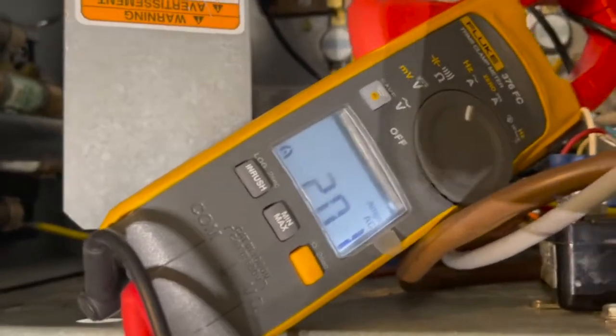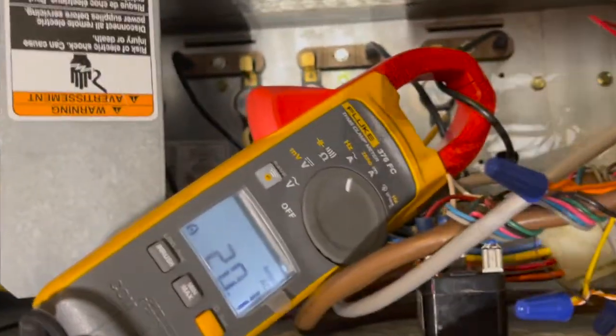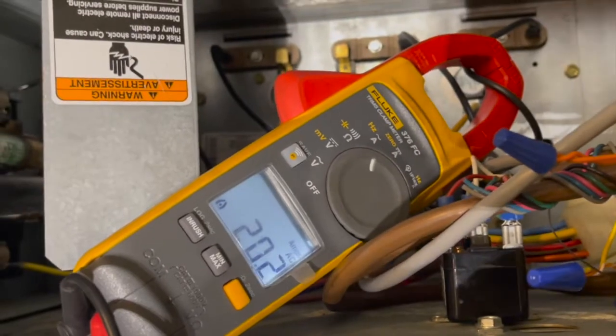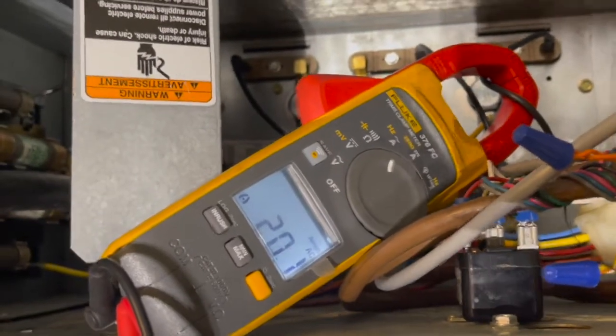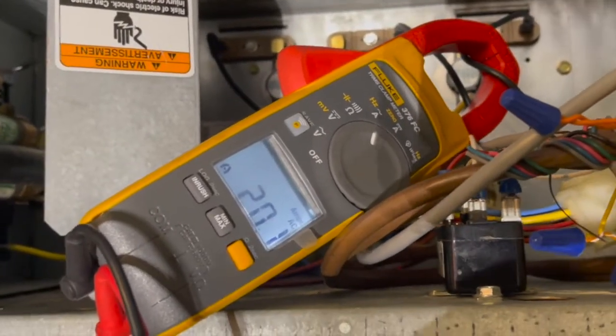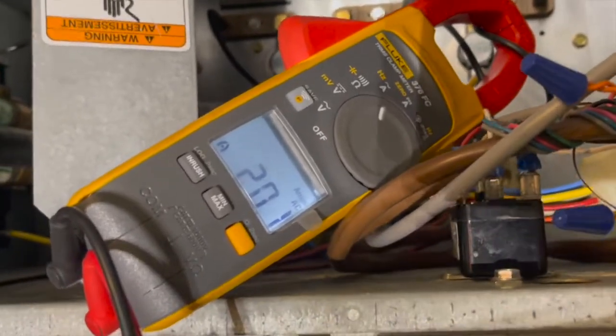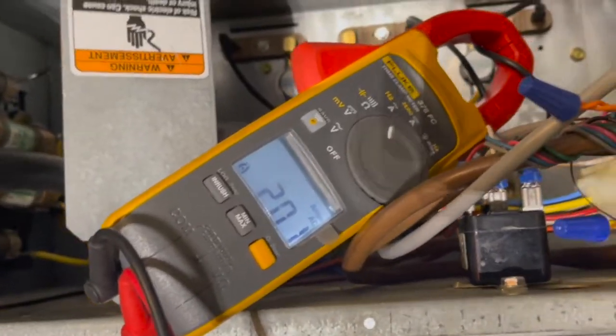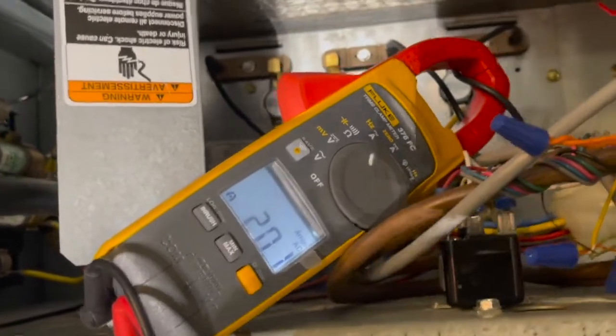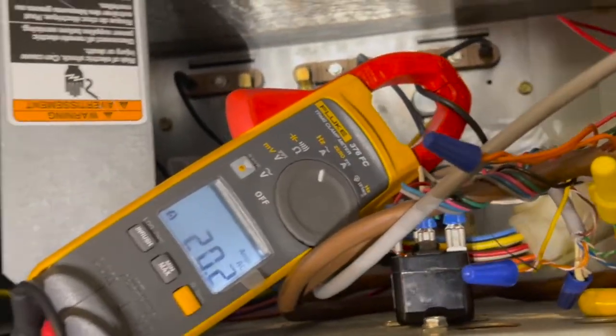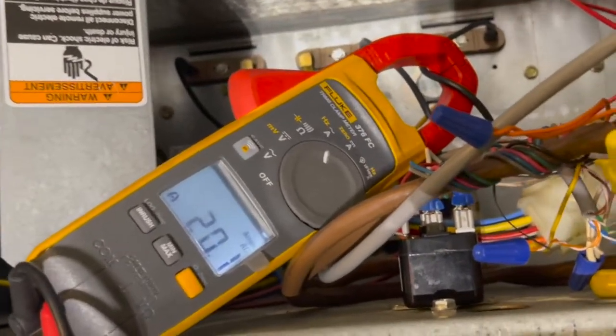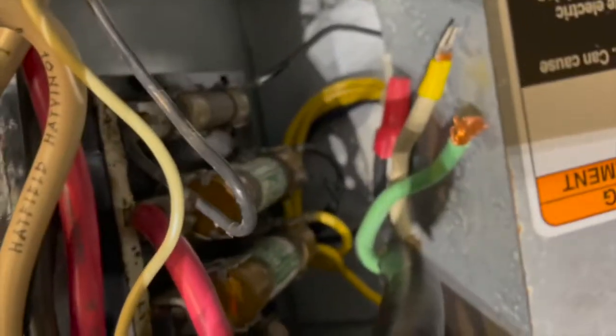So again, circuit breakers might be rated at a certain amp reading, but in reality you can never go up to that amp reading. You're supposed to go, I think, 5 amps below it or whatever. There's a data sheet on each circuit breaker telling you its thermal overload capabilities. So that's why you never want to run a circuit breaker at max load right at 60 amps. Same with those fuses, those are 60 amp fuses. But at least it's working.